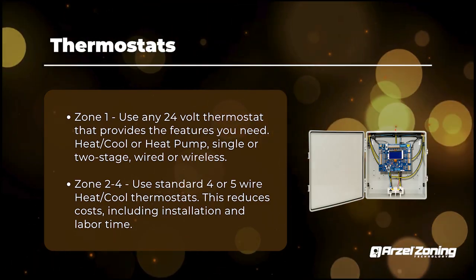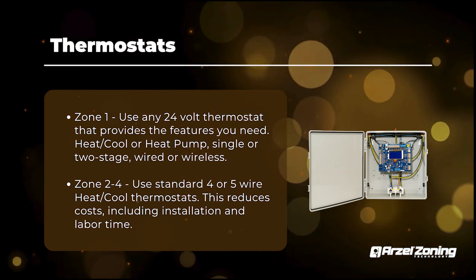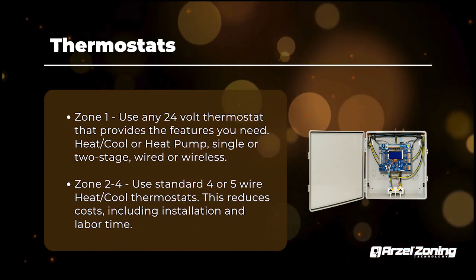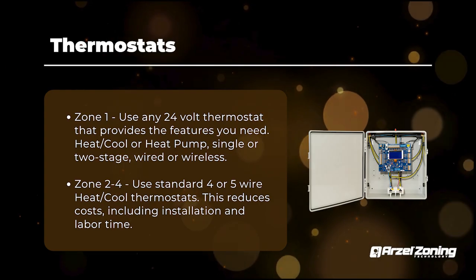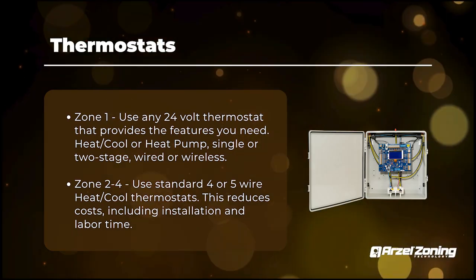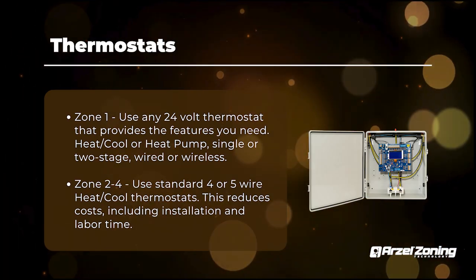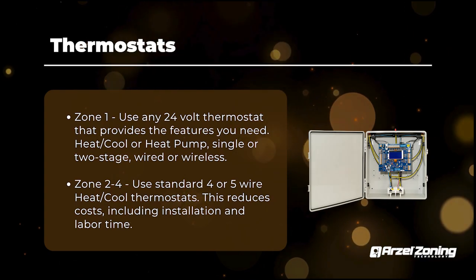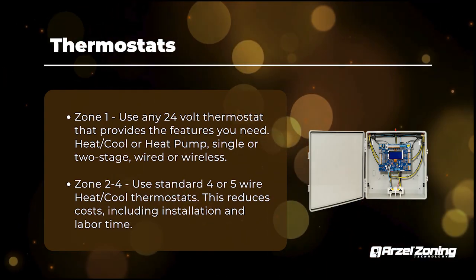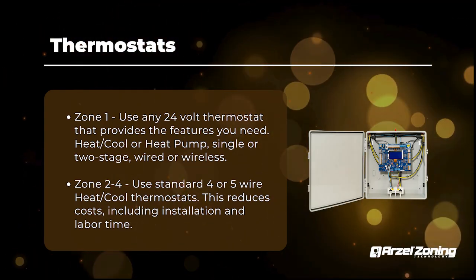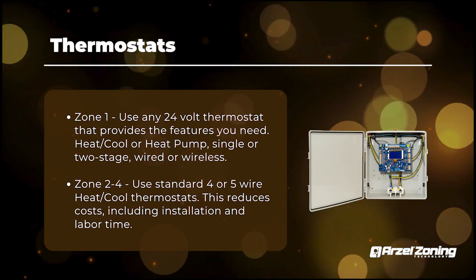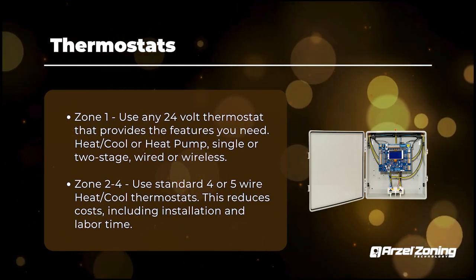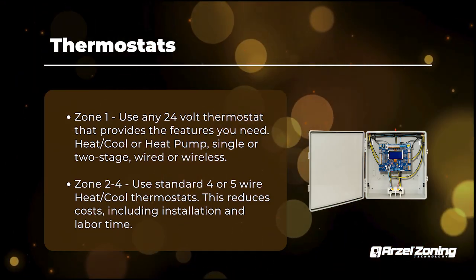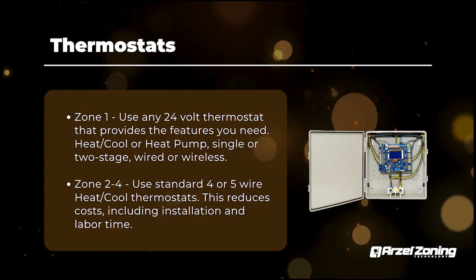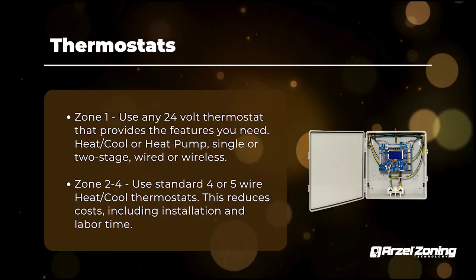If you use a heat cool thermostat, you can do just a normally open switch, and it'll go to your zone 1 terminal strip between R and E, and then essentially when the customer flips that switch, it would lock the panel in emergency heat and output for your backup heat source. So it's really up to you how you want to achieve that auxiliary heat function. You can let the panel do it. You can use that heat pump thermostat with the emergency heat terminal. So it really depends on how you want to achieve it, but you have both options as far as thermostats are concerned.